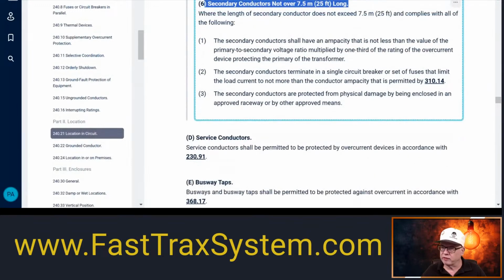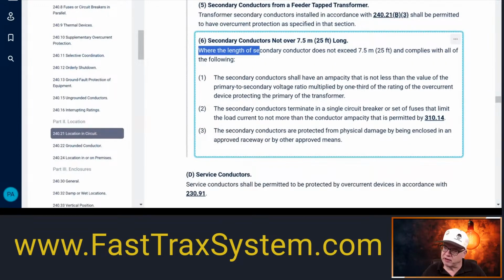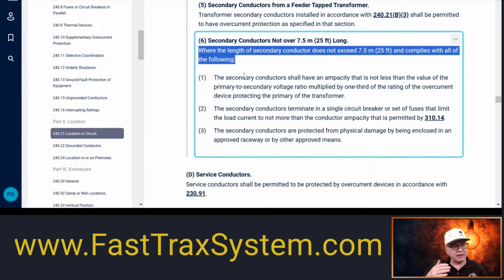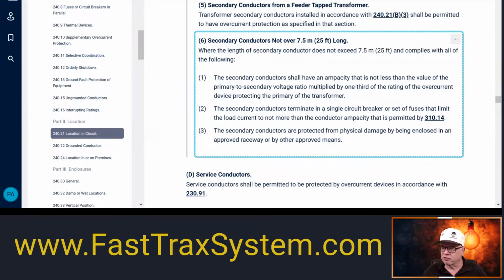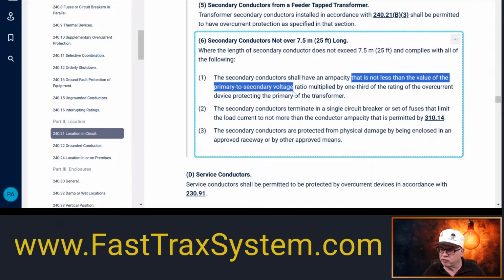Okay, what are the rules? It says, where the length of the secondary conductor does not exceed 25 feet and complies with all of the following. So in order to get that 25-foot length from the secondary side of that transformer, to get that 25-foot advantage of this conductor length, we have to follow these rules. The first one says the secondary conductors shall have an ampacity. So it's telling me we have a minimum ampacity requirement here. Shall have an ampacity that is not less than the value of the primary to secondary voltage ratio.